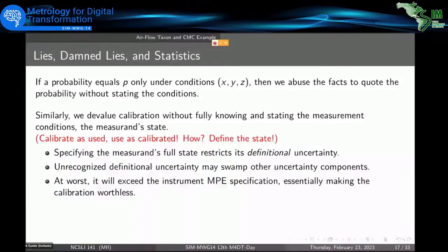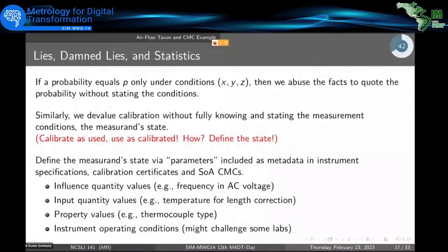In the worst case, our definition of the Measurand is so bad compared to how the instrument is used that it swamps out the accuracy specification and makes the calibration worthless. So to avoid that, we want to fully describe the Measurand state. That involves the influence quantities, input quantities, any property values, or relevant operating conditions. So this becomes part of our CMC template.